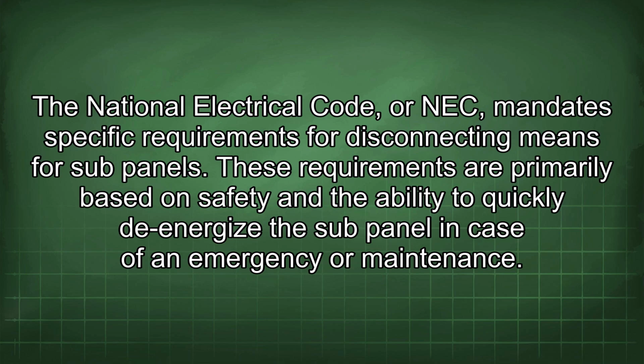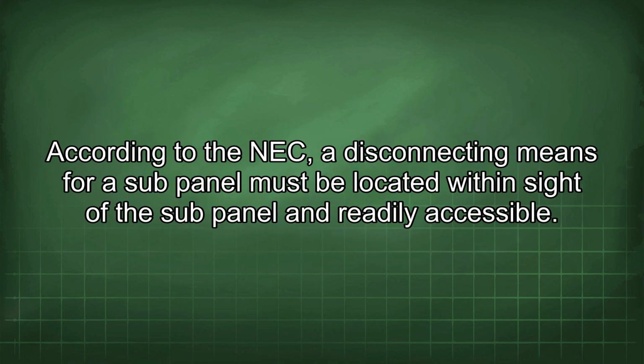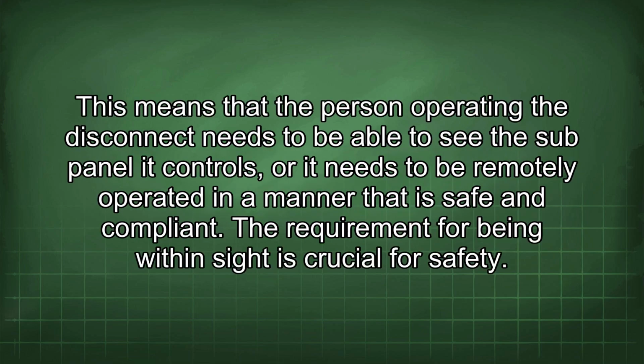These requirements are primarily based on safety and the ability to quickly de-energize a sub-panel in case of an emergency or maintenance. According to the NEC, a disconnecting means for a sub-panel must be located within sight of the sub-panel and readily accessible. This means that the person operating the disconnect needs to be able to see the sub-panel it controls, or it needs to be remotely operated in a manner that is safe and compliant.